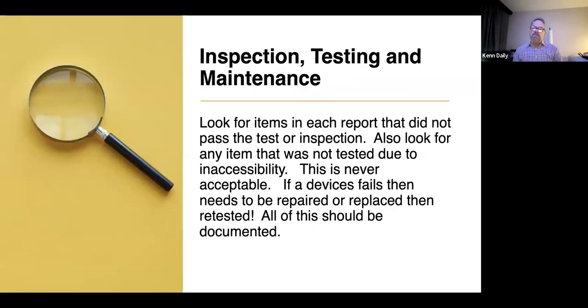And then the other really important thing, for those of you who are listening, whether you're maintenance, administration, or quality staff, is that you need to make sure you're reading and reviewing all the documentation you are getting from vendors, whether it's sprinkler, fire extinguisher, range hood, whatever you're using a vendor to do rather than doing yourself. Please review that to make sure it is completed. Any work that they've asked for or required you to do, you need to make sure it's done to close the loop on that inspection, testing, and maintenance document. Otherwise, if it's not done, the surveyors will find you in non-compliance because you did not follow up on any repairs or recommendations.